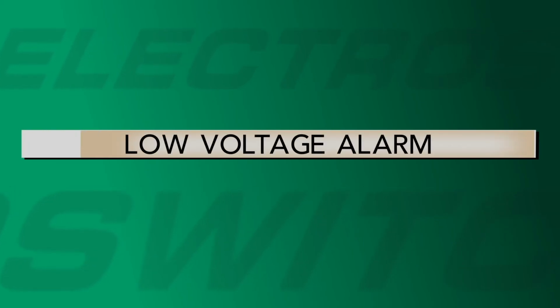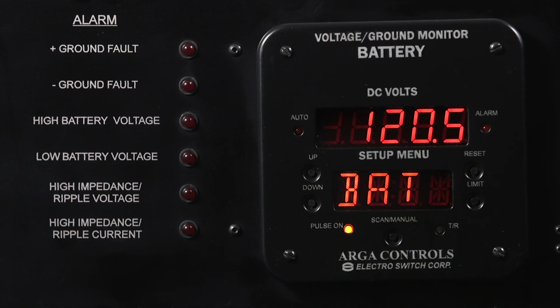The same will occur as I decrease the battery voltage to the low voltage alarm of 105 volts DC. An alarm LED on the top right area of the battery monitor will activate, and subsequently a corresponding low voltage alarm LED will illuminate on alarm outputs to the left of the meter for the rack-mounted battery monitor.